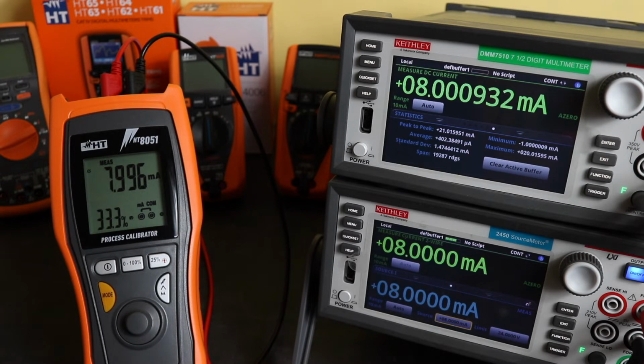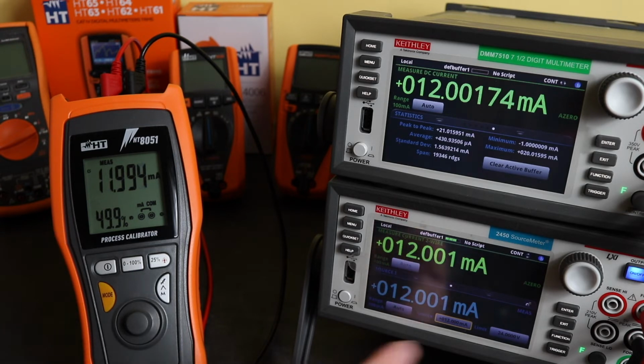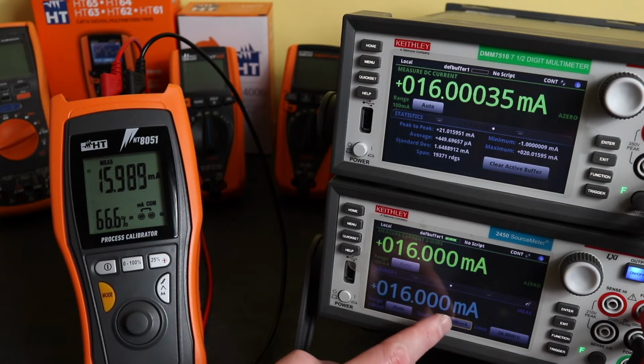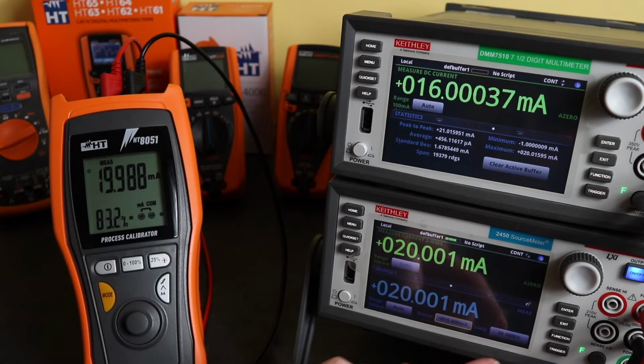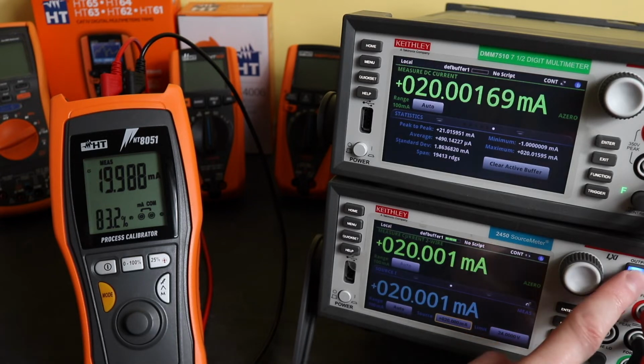So a fast response from it, but 7.996, again a little bit low in comparison to the 8.0009 displayed on the bench meter there. Let's go 12 milliamp. So we've had to go up a range now, and we're on 12.001, which matches across both instruments, but we're on 11.994, displaying 49.9%. Let's go to 16, which is 15.99. Dead 16.000. So you can see the instrument appears to be reading slightly lower than both of these instruments. 19.988 in comparison to 20.001 at the full 20 milliamp loop current there. So I'll just knock that off and we'll reset everything to measure voltage.